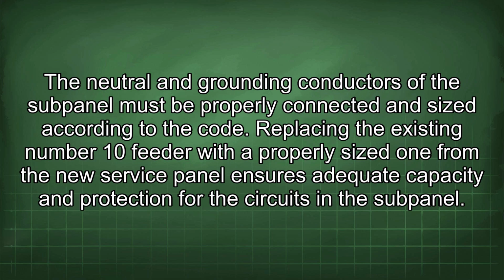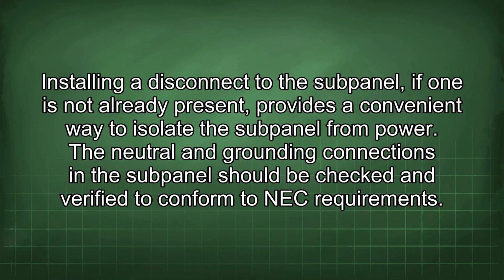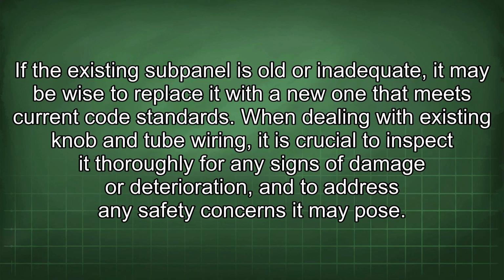Replacing the existing number 10 feeder with a properly sized one from the new service panel ensures adequate capacity and protection for the circuits in the subpanel. Installing a disconnect to the subpanel, if one is not already present, provides a convenient way to isolate the subpanel from power. The neutral and grounding connections in the subpanel should be checked and verified to conform to NEC requirements. If the existing subpanel is old or inadequate, it may be wise to replace it with a new one that meets current code standards.